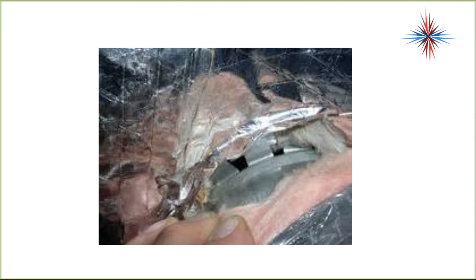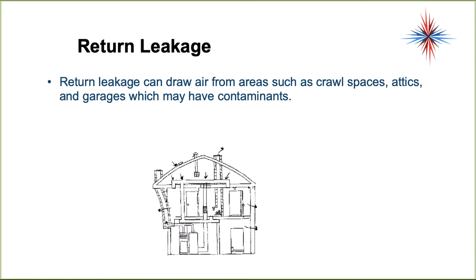Here's a picture of supply duct leakage buried under insulation — a photo from an insurance claim involving mold in a house. It shows a duct connector between two pieces of ductwork where someone did not put the connector together properly and did not tape it, leaving holes all over it. That ductwork is leaking. Return duct leakage can draw air from contaminated areas such as crawl spaces, attics, and garages, pulling it through the air handler and pushing it into the house — actually over-pressurizing a house with contaminated air.